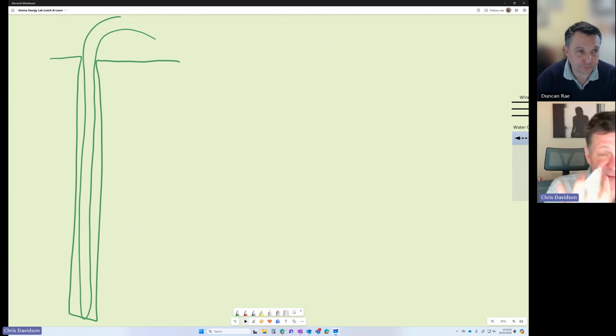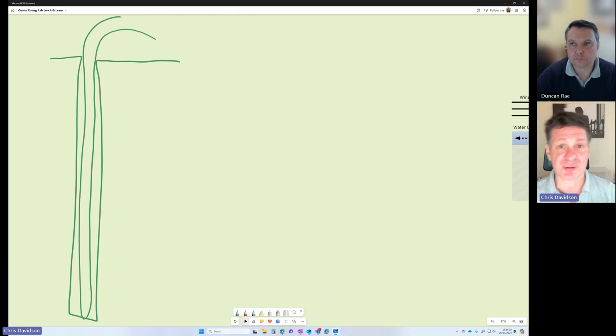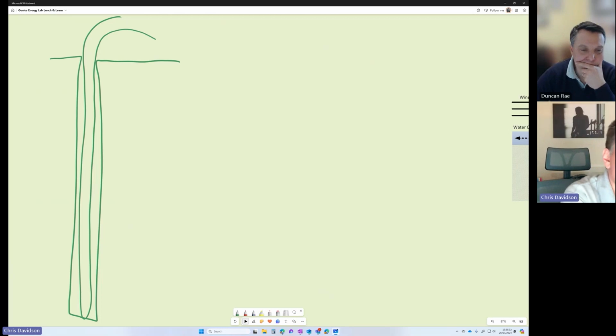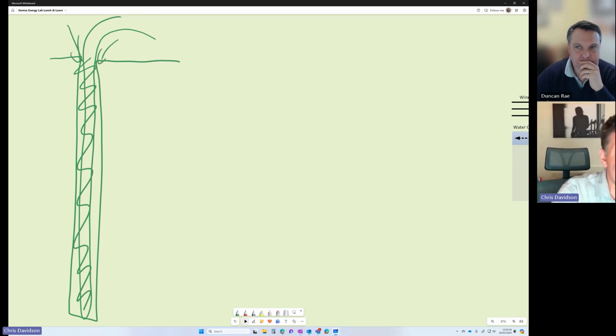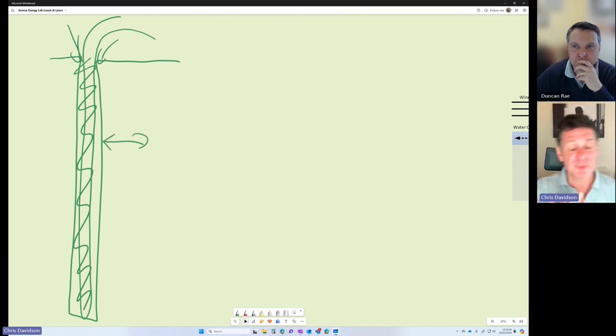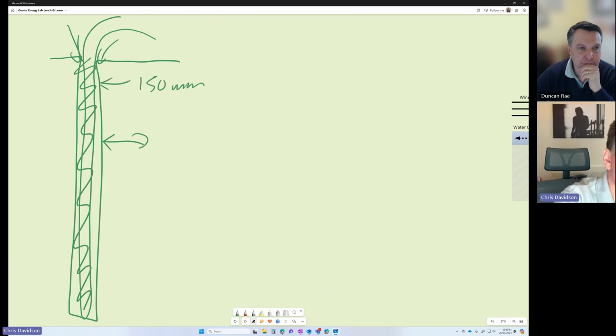That water is treated with an antifreeze and a biocide to ensure it remains healthy and doesn't freeze throughout the operation. The borehole is completed with a cementitious grout material, and that grout stops anything getting down that borehole, potentially polluting an aquifer down there, and it also gives us thermal contact to and fro with the ground around it. Diameter of these boreholes is typically 150 millimeters, and typical depths are somewhere between 100 and 300 meters deep.